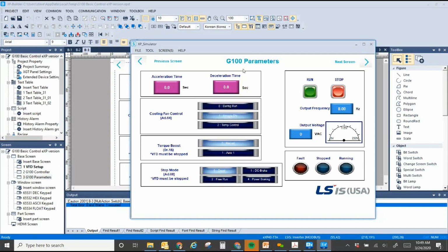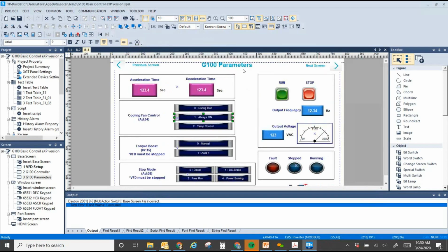You could turn the fan off and on, and if I was connected to a drive right now with my HMI all set up, I could turn the fan off and on. Someone could hear the fan starting and stopping. You'd be able to hit your run button here and see your output voltage go up and down on this little virtual analog meter. We also have some faults and statuses for stopping and running.